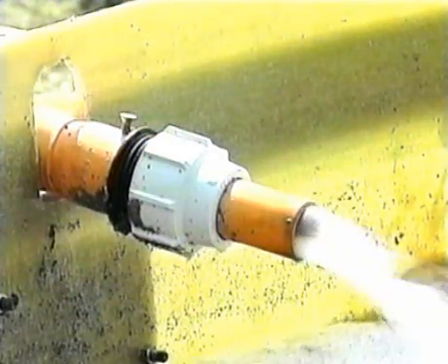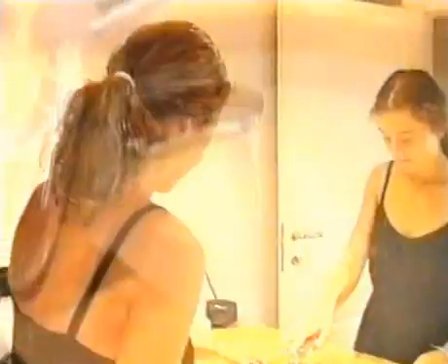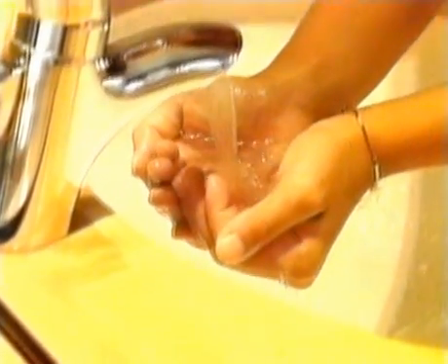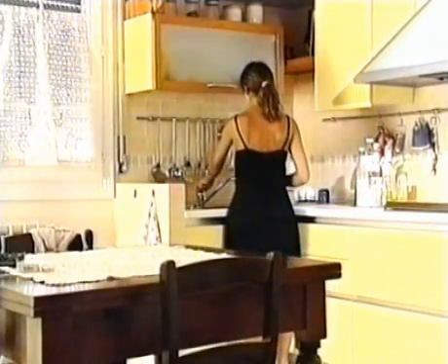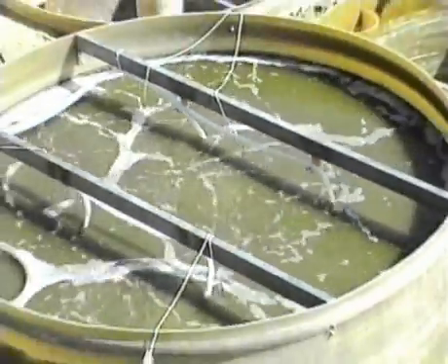The size of the chambers is based on the concept of the standard inhabitant, which defines the specific load of the inhabitant in both hydraulic and organic terms. To be on the safe side, the size of the disposal system is based on the maximum values encountered. The water supply needed for washing and waste disposal is approximately 200 litres per person per day, and the organic load is about 75 grams of biochemical oxygen demand per person per day.